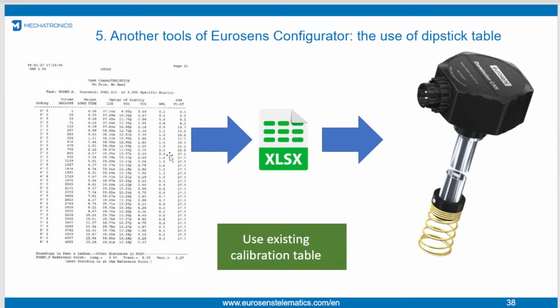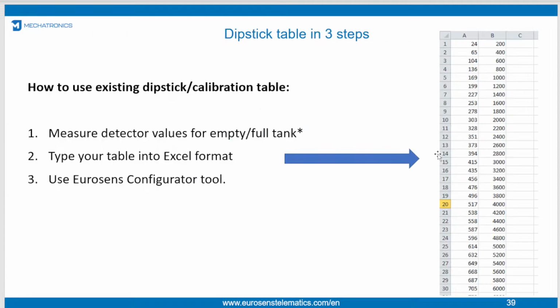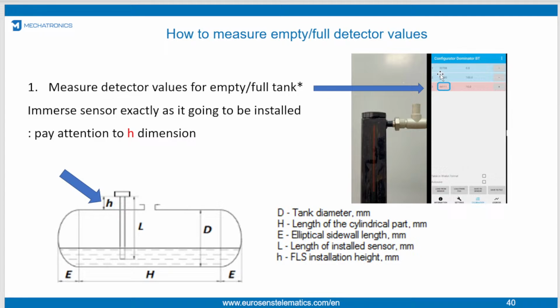All you need is to type this data in Excel in the format level and volume, in any units, inches, meters, no matter. Then you need to know again the empty and full detector values of the sensor which you will fit in the tank. So you need a tube. You don't need to fill the big fuel storage, you need only to have a tube and calibrate the sensor empty and full to know these values.